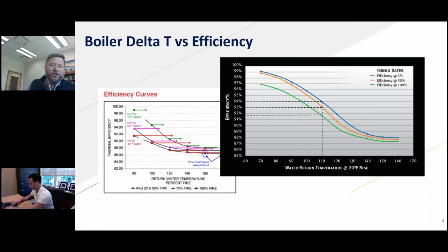We can do that in New York. I happen to live in Wisconsin, where it gets even colder. We routinely heat buildings here with 100 or 110 degree hot water, even though we get down to minus 20 or minus 30 degree outdoor temperature. And so we don't necessarily need to provide those high hot water temperatures. And so over time, that has changed.